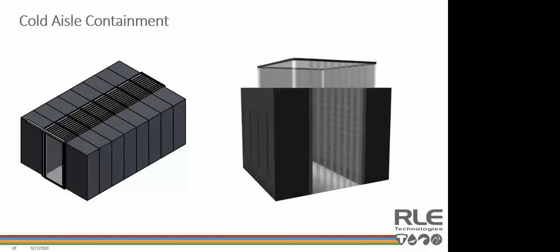Cold aisle containment typically consists of doors on the ends of the aisles and either a containment ceiling directly over the racks or soft curtain style containment that extends from the tops of the server racks to the ceiling. The cold air should only be allowed to exit the space through the server racks. This allows the rest of the data center to become the hot air return. Cold aisle containment typically doesn't require a return air plenum in the ceiling, which significantly simplifies the installation and reduces cost.